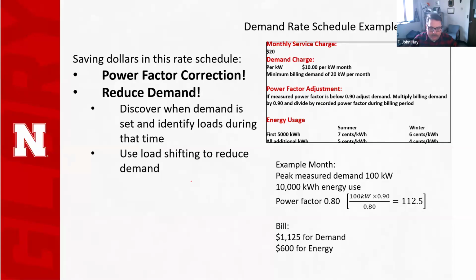So let's go back and figure out how that might work out. Back down to the lower right-hand corner. If our measured power factor is 0.8, I take my billing demand of 100 times 0.9, divide by 0.8, I get 112.5. Instead of being billed for 100 kW, I'm now going to be billed for 112.5. My low power factor adjusted up my demand so that I pay 1,125 for demand and 600 for energy. That's generally how power factor charges appear and are calculated on your bill.